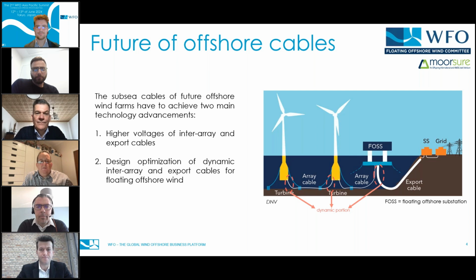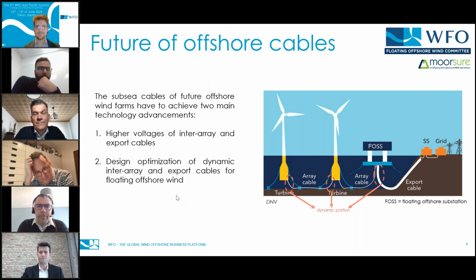Some key takeaways from the white paper on Dynamic Cables that we released in February: we looked at the future of offshore cables, setting the scene for what the purpose of offshore dynamic cables is. There will need to be two main technological advancements: a need for higher voltage of inter-array and export cables as power requirements increase, with efficiency needing to improve by moving to higher voltages; and design optimization for dynamic inter-array and export cables, looking at technical risks as well as reducing OPEX and CAPEX considerations.